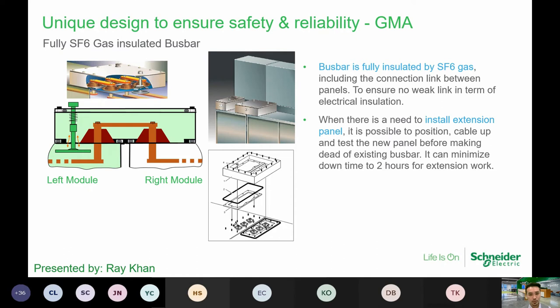It also helps in terms of predictive maintenance. With the fully SF6 gas insulated busbar, the module on the left can actually draw vacuum. Once the vacuum process takes place, you remove the moisture and also the dust particles. Once the vacuum is fully created inside the box, we can see there's a plunger. The plunger will then open, allowing the SF6 gas to fill up the box. That's where you can see the two colors as an indication of the SF6 gas. So it shows the simplicity of installing this box for panel expansion.